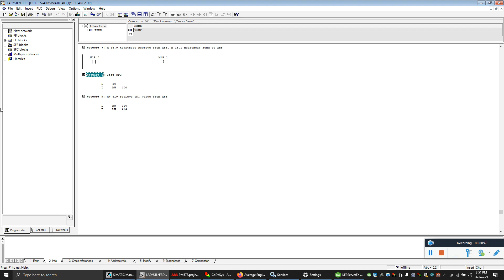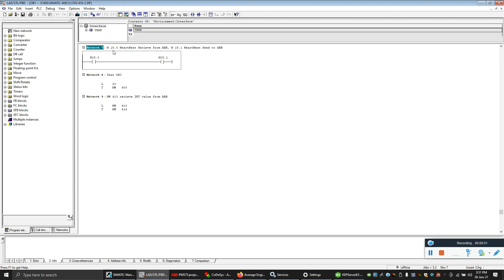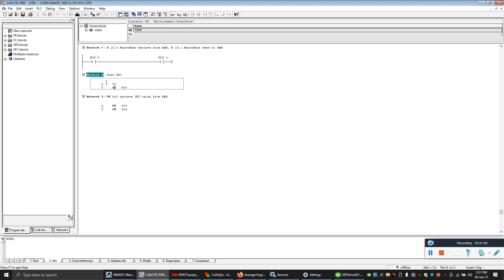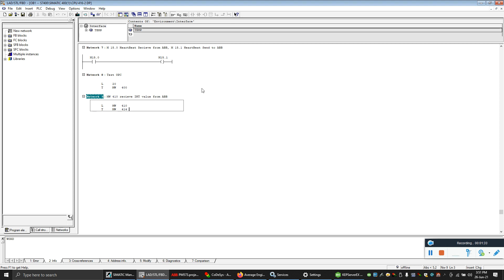Basically I made a small program where I'll be sending a heartbeat — an on/off bit — from ABB, and my M15.0 bit will receive that heartbeat. I will send back the heartbeat from M15.1. I'm loading value number 22 into MW400, and when I configure my OPC server I can verify I'm getting some value in MW400. MW410 is the integer value I'm going to receive from ABB.